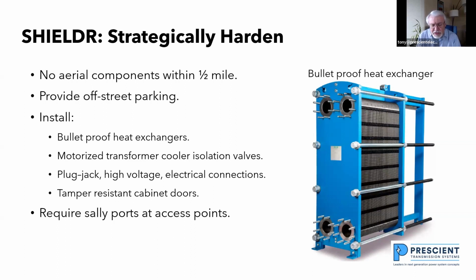And the bulletproof heat exchanger on the slide here, this is one that we've put a metal barrier around the cooling fins. And this is a partial view of what one would look like. We should be putting in motorized transformer cooler isolation valves. Shooting a hole in a cooler doesn't really damage the transformer. What happens is the oil drains down, and then you lose insulation strength inside the transformer, and a surge occurs and the transformer fails. So if we recognized that we were losing oil out of a transformer, we would operate transformer cooler isolation valves, button the transformer up, minimize the possibility of transformer failure.